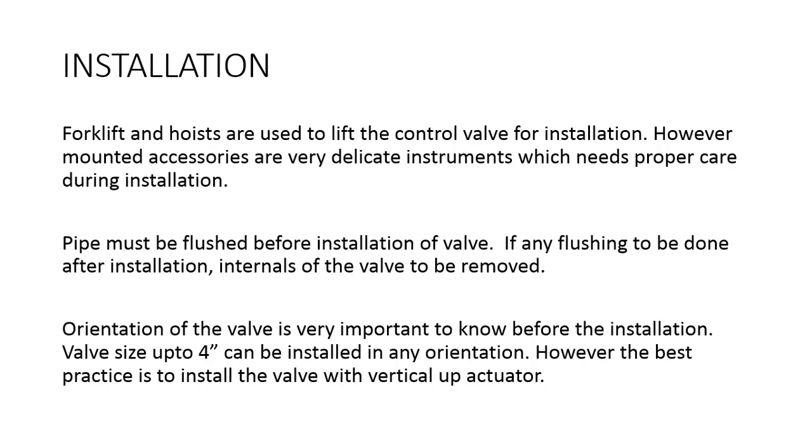Next is the installation at site. Forklift and hoist are used to lift the control valve for installation. However, mounting accessories are very delicate instruments which need proper care during installation. Pipe must be flushed before installation of valve. If any flushing is to be done after installation, internals of the valves must be removed. Many times we see that welding rods and tool spanners are found inside the pipeline or valves. Hence, flushing must be done properly.